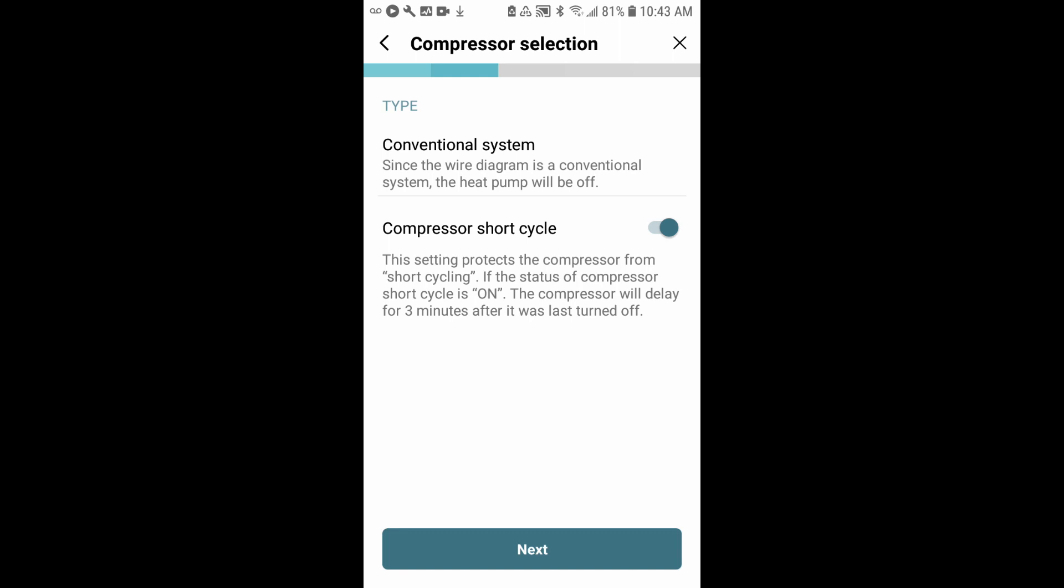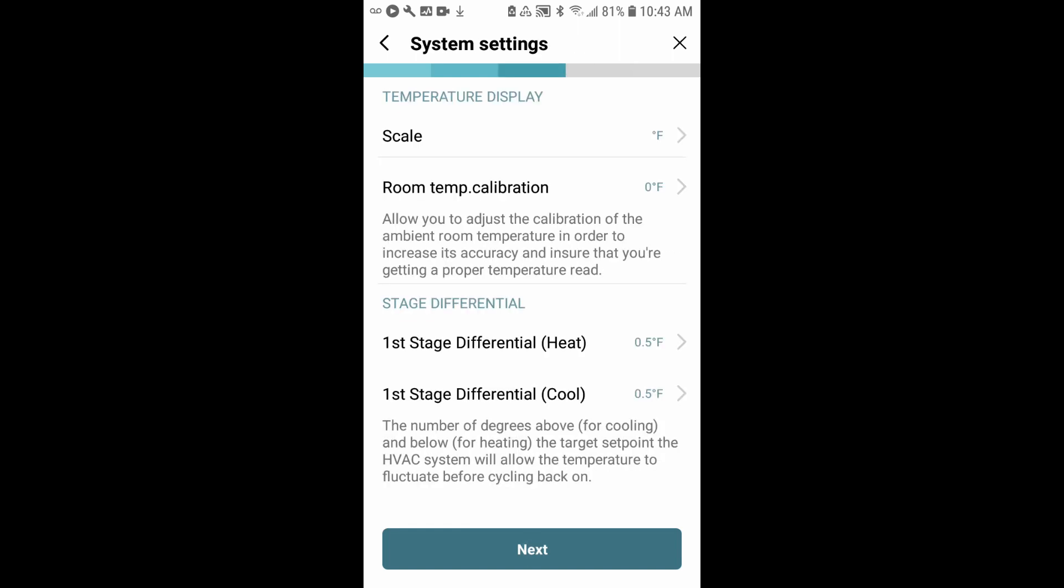This is compressor selection. It's just confirming that you're a conventional system, and you'll leave compressor short cycle on. This is really a protection to prevent damage to your system in the long term. It'll just delay the compressor for three minutes. We'll go ahead and leave that on and hit next.